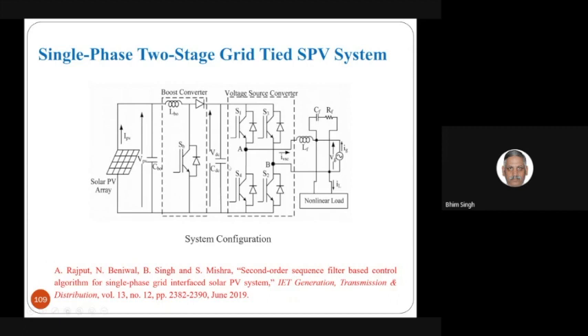The benefit of two-stage is that you can take the panel voltage equal to the voltage rating of your DC link, because the boost converter is there. In the previous case, you have to take the PV voltage much higher, 15 to 20%. So all the devices are exposed to around 20% higher voltage rating, at which they are utilized only for the nominal voltage rating. So that's the benefit here: the voltage rating of all the devices is reduced compared to a single stage system.